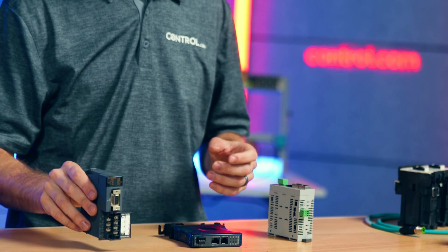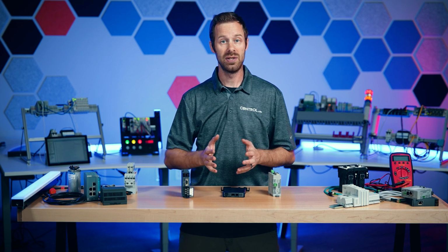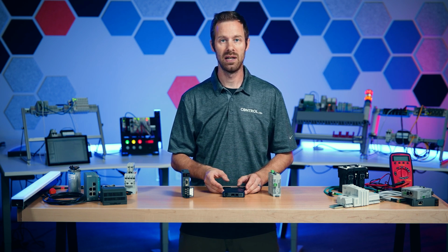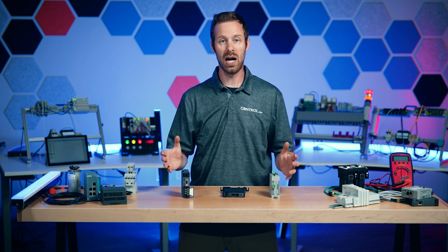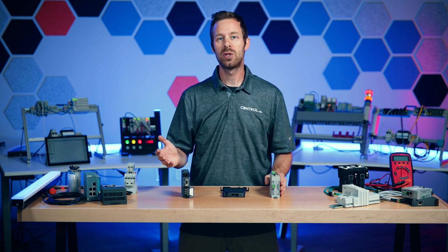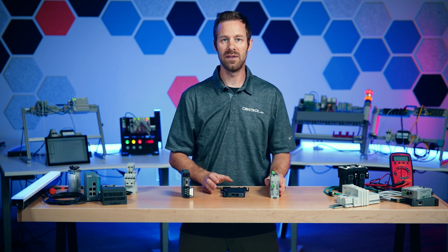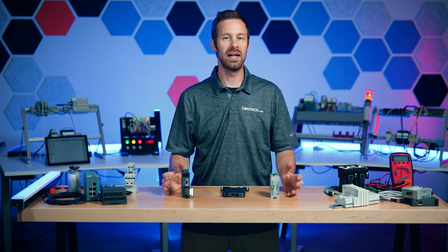Each one is labeled and we can find the pinouts for those, but the RS-485 standard determines voltage signals, voltage levels, speeds, and distances that we can configure a network protocol to ride on top of, such as Modbus, to allow the right kind of data to be traveling over that RS-485 standard and give us a reliable network across our entire facility.